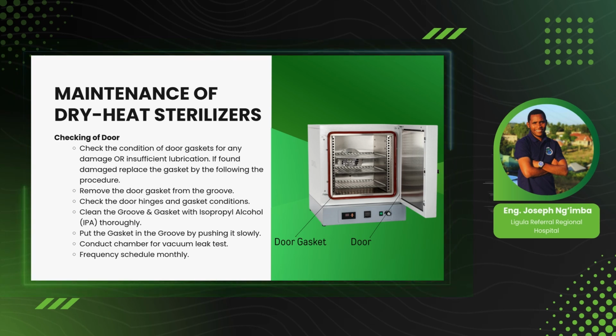So how can you remove and replace the gasket? The gasket sits in the door groove. You need to carefully remove it and check if you can see any corrosion or damage. If there is damage or corrosion, you have to replace it using the same procedure. You fix it into the door groove slowly, using a special lubricant, for example silicone gel, which you can spray on the door groove where the gasket lies. You can also conduct a chamber inspection, and if there is a need to clean the chamber, you clean it. This kind of maintenance is done on a monthly basis, and it is described here with the help of a picture where you can see the gasket and the door. When you close the door, they come together to make a good seal.